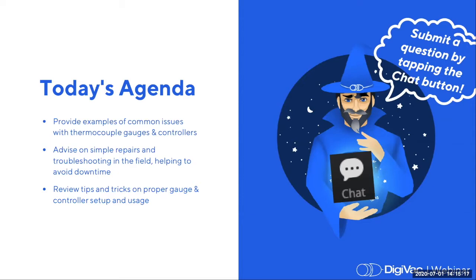Today's agenda will include providing examples of common issues with thermocouple gauges and controllers, such as power problems, inaccurate readings, or problems with accurate vacuum control. Then we'll advise on simple repairs and troubleshooting in the field, hoping to avoid downtime. Then we'll review some tips and tricks on proper gauge and controller setup and usage for anybody new to our instruments or their industry. We'll be focusing largely on thermocouple type gauges in this webinar, which make up a large percentage of gauges on the market and in our product line.